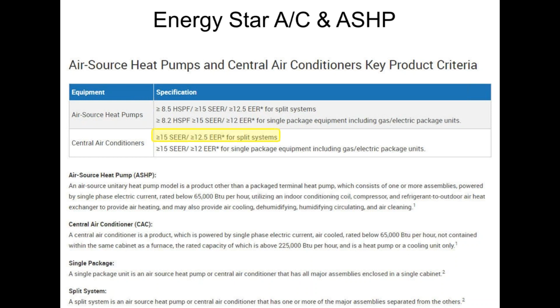But for a split system, you have to meet two things. You have to be 15 SEER and you have to be 12.5 EER. EER, as you know, is the full load efficiency. SEER is the seasonal efficiency, so basically it takes into account part loading. So you have to do both of those. It's not one or the other, it is both. If you have a package unit, it's slightly different. It's 15 and 12 instead of 15 and 12.5. Very similar. If you have a heat pump, it's still those same numbers. You still have to be 15 SEER and 12.5 EER for a split system heat pump. Plus, you have to be efficient on the heating side. HSPF, heating seasonal performance factor, needs to be 8.5 for a split system. You get that one extra spec requirement if it's a heat pump versus an air conditioner. So hopefully that makes sense to everybody.